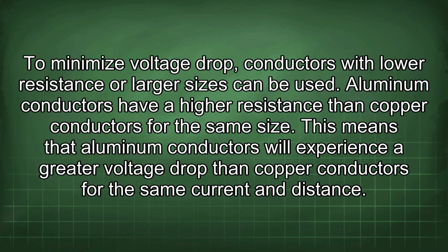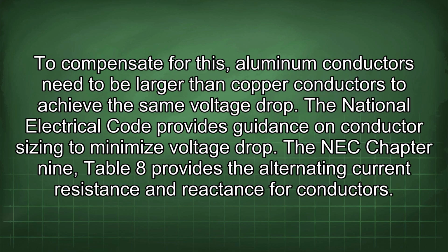Aluminum conductors have a higher resistance than copper conductors for the same size. This means that aluminum conductors will experience a greater voltage drop than copper conductors for the same current and distance. To compensate for this, aluminum conductors need to be larger than copper conductors to achieve the same voltage drop. The National Electrical Code provides guidance on conductor sizing to minimize voltage drop. The NEC Chapter 9, Table 8 provides the alternating current resistance and reactance for conductors.